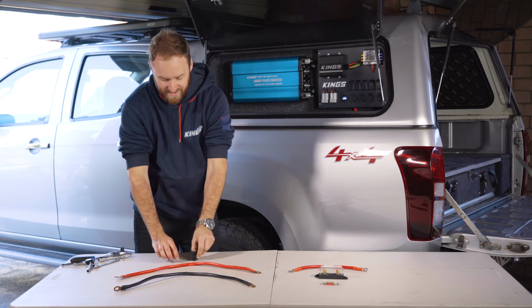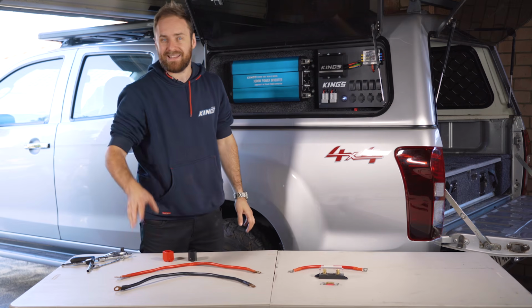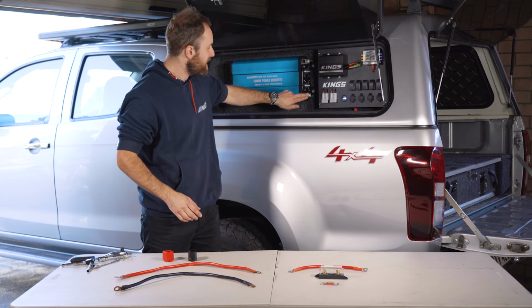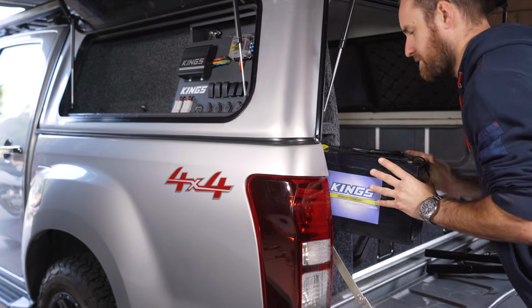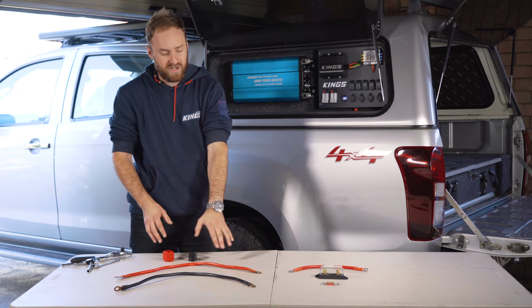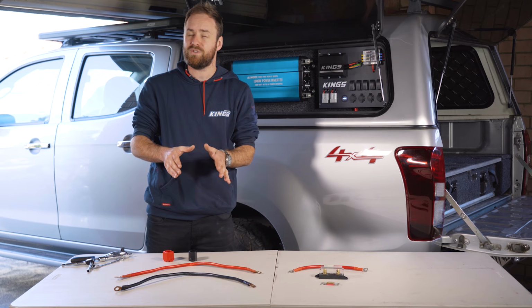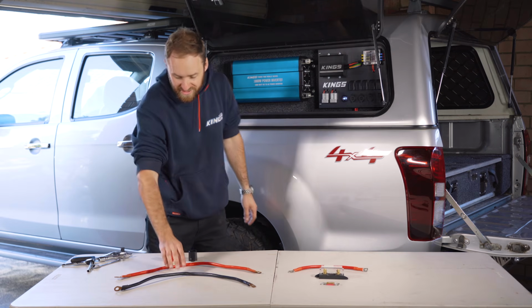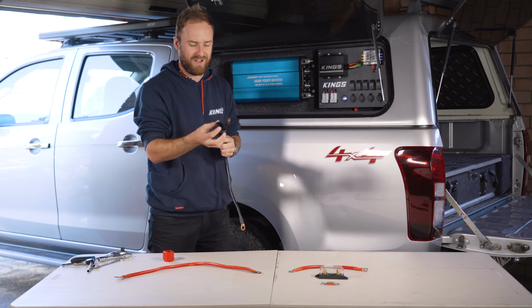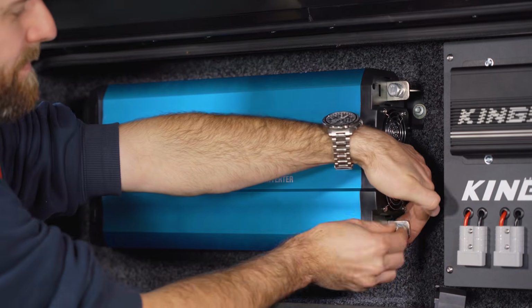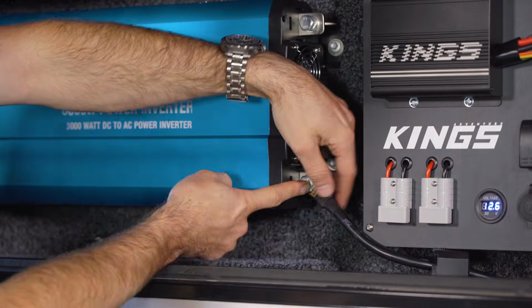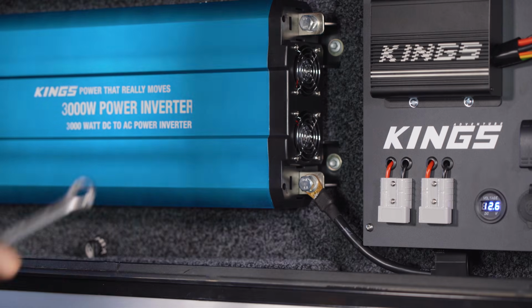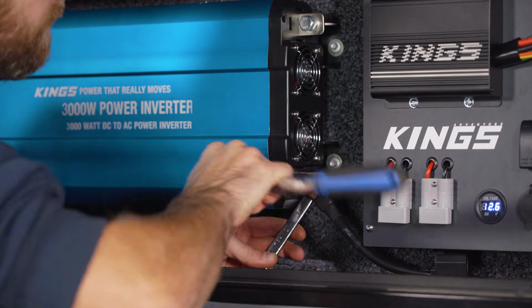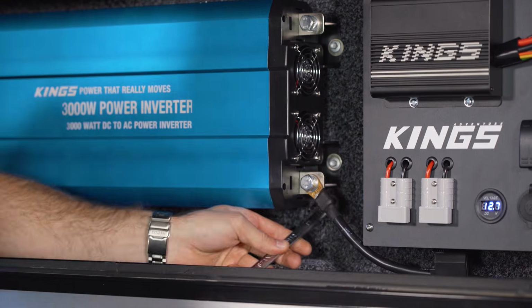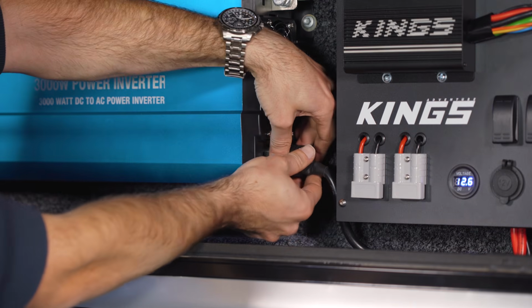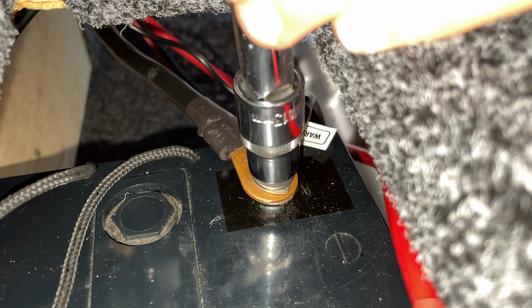Now, the easy part, the wiring. So I've got my black negative wire here, and that needs to run from the earth terminal of the inverter into my battery, which is underneath here. Then with the positive, I'm gonna add my fuse holder, but leave the fuse out until the final step. So the first thing you need to do, grab your earth and make sure you slide this protective cover on. Loosen off the included nut and bolt, and then mount that earth cable straight to the terminal, making sure you've checked it is marked negative. You'll need a 17mm socket or spanner to tighten them up. Refit that protective cover, then mount the other end to the negative terminal of your battery.